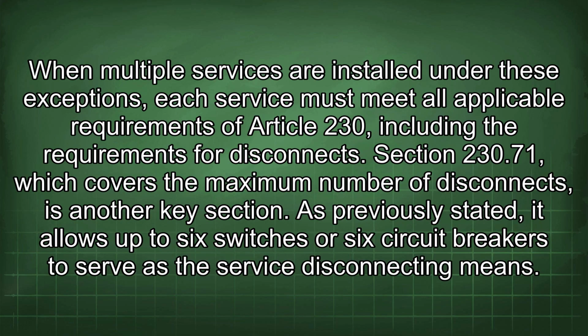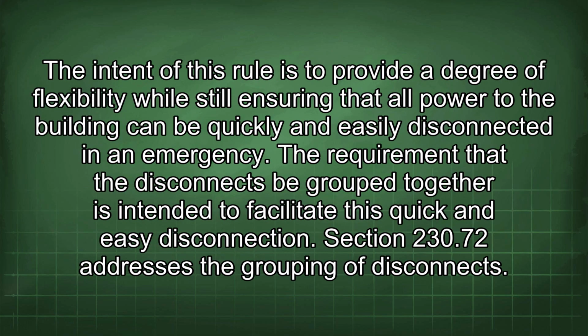When multiple services are installed under these exceptions, each service must meet all applicable requirements of Article 230, including the requirements for disconnects. Section 230.71, which covers the maximum number of disconnects, is another key section. As previously stated, it allows up to 6 switches or 6 circuit breakers to serve as the service disconnecting means. The intent of this rule is to provide a degree of flexibility while still ensuring that all power to the building can be quickly and easily disconnected in an emergency. The requirement that the disconnects be grouped together is intended to facilitate this quick and easy disconnection.